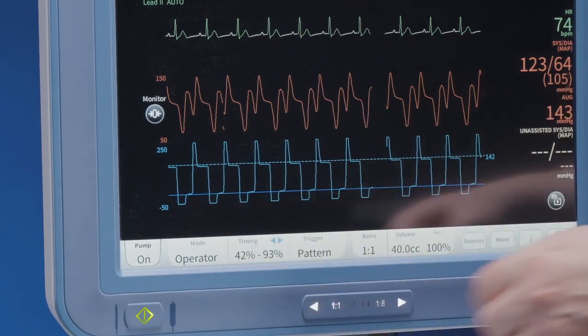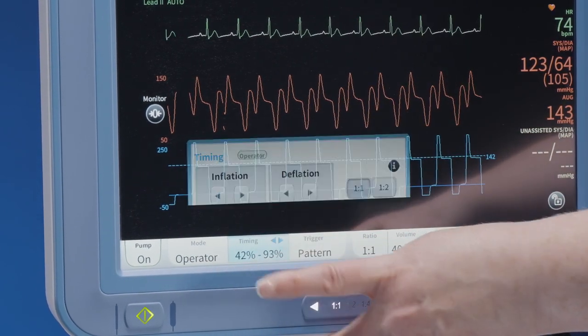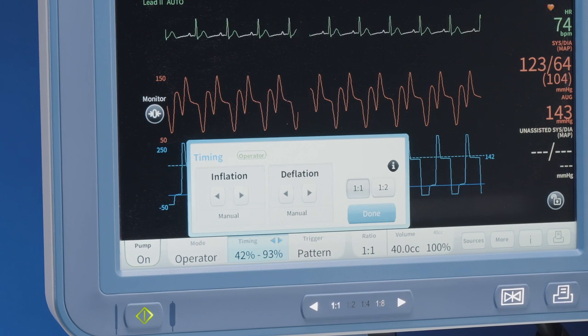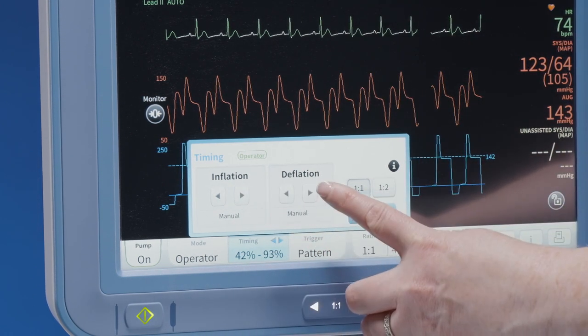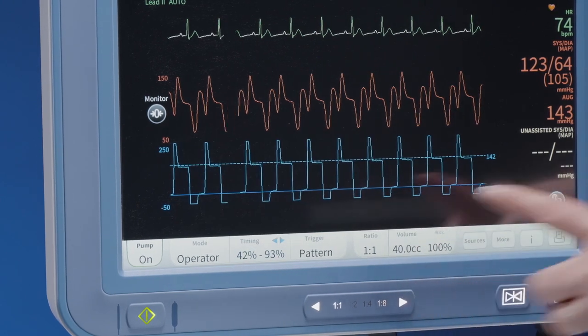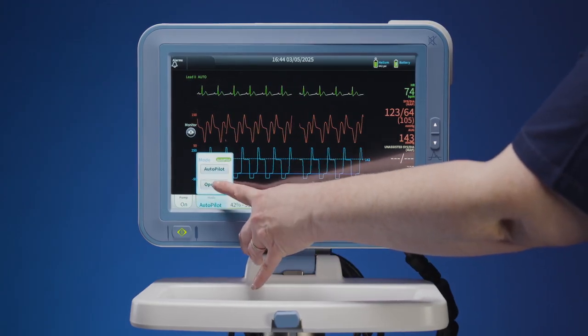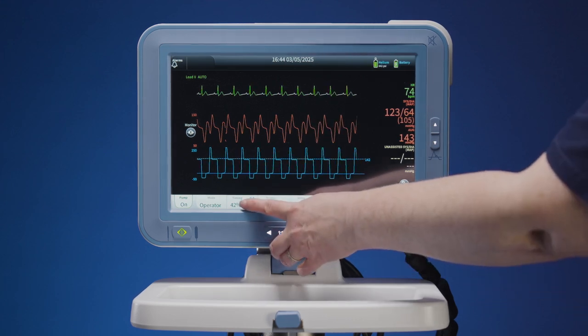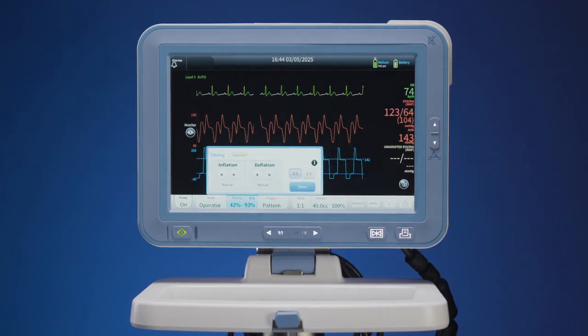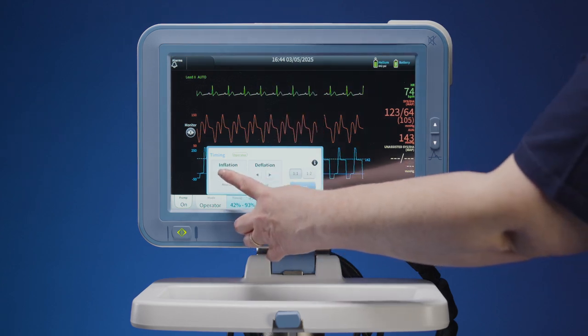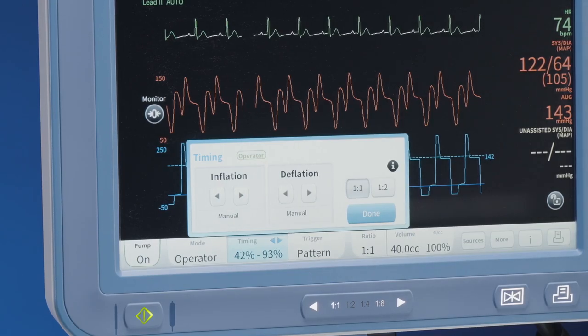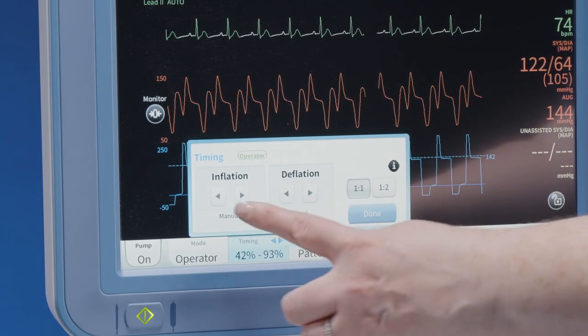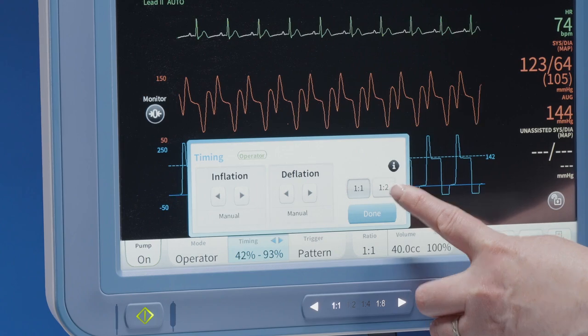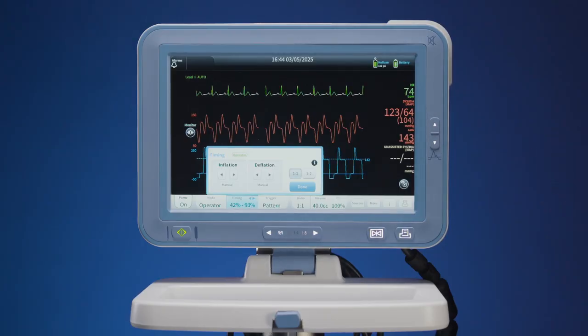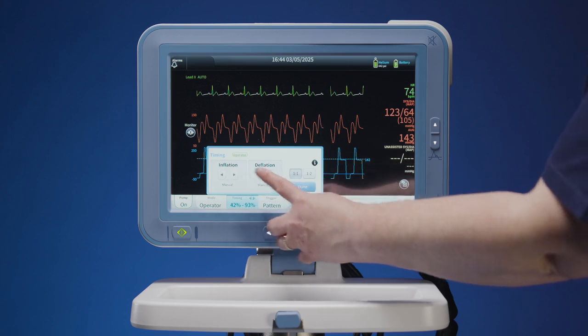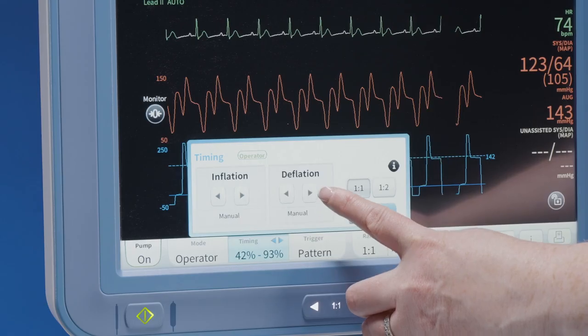In operator mode, a clinician can select and set most IABP functions. This will include selecting trigger and timing adjustments. The balloon pump will not override user settings. Timing must be adjusted by the user in operator mode. The timing controls will be displayed when the user presses the timing key. Even in the operator mode, the timing will automatically adjust for heart rate changes within 25%. The arrow keys adjust the inflation and deflation timing in 1% increments. There is an earlier and later key for each setting. Since timing assessment should be done in a 1:2, the assist ratio selections for 1:1 and 1:2 are also displayed in this menu.